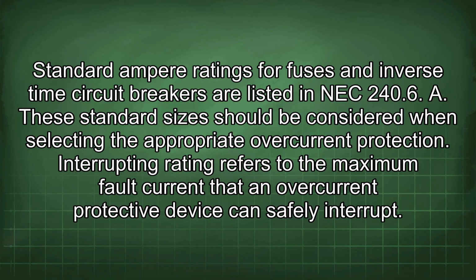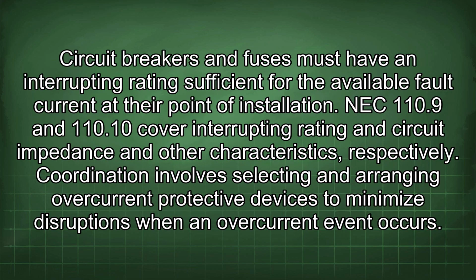Interrupting rating refers to the maximum fault current that an overcurrent protective device can safely interrupt. Circuit breakers and fuses must have an interrupting rating sufficient for the available fault current at their point of installation. NEC 110.9 and 110.10 cover interrupting rating and circuit impedance and other characteristics, respectively.